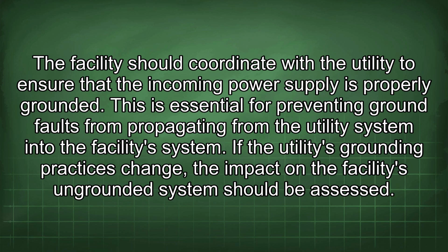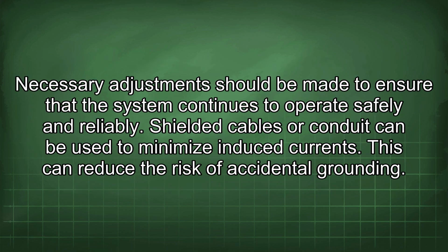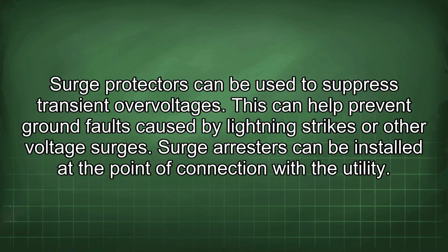If the utility's grounding practices change, the impact on the facility's ungrounded system should be assessed. Necessary adjustments should be made to ensure that the system continues to operate safely and reliably. Shielded cables or conduit can be used to minimize induced currents. This can reduce the risk of accidental grounding. Surge protectors can be used to suppress transient overvoltages. This can help prevent ground faults caused by lightning strikes or other voltage surges.